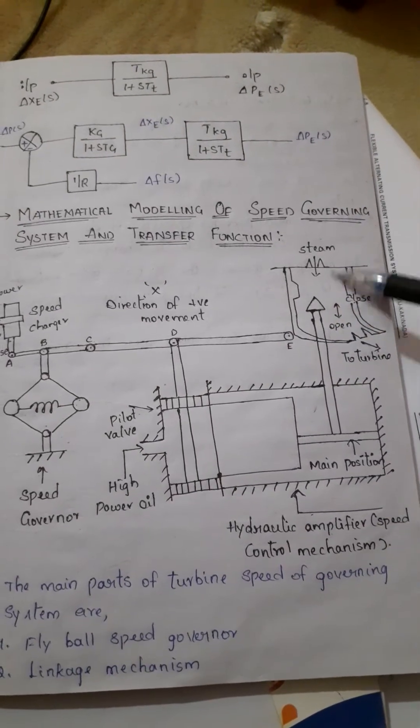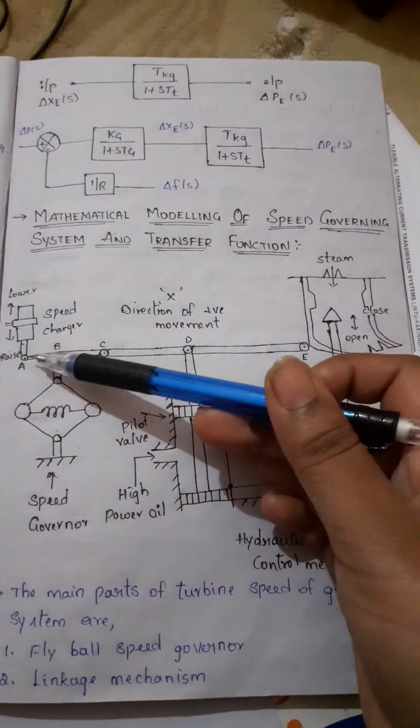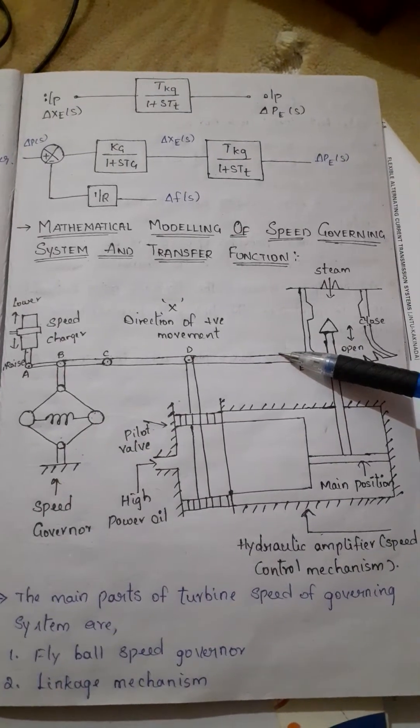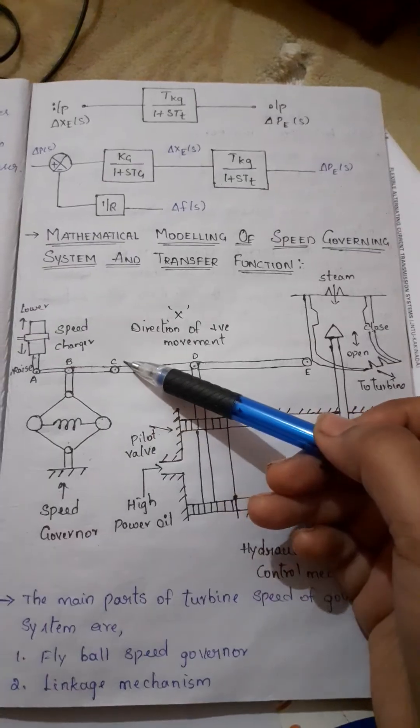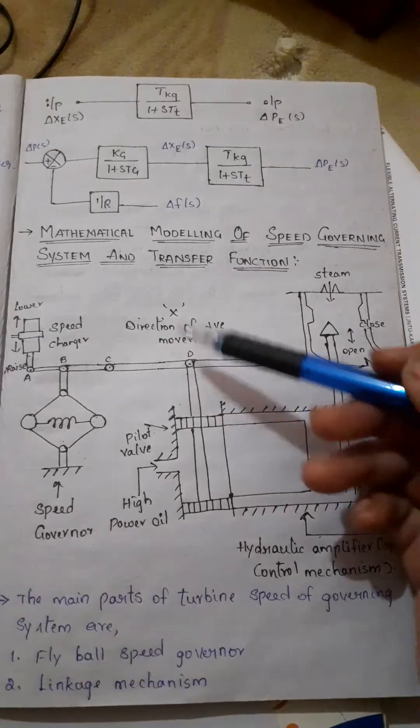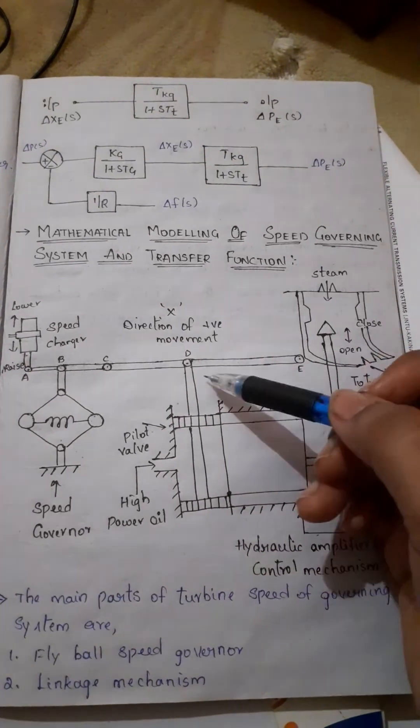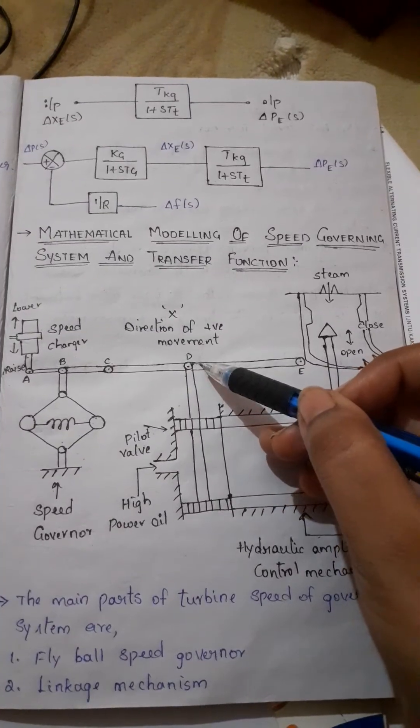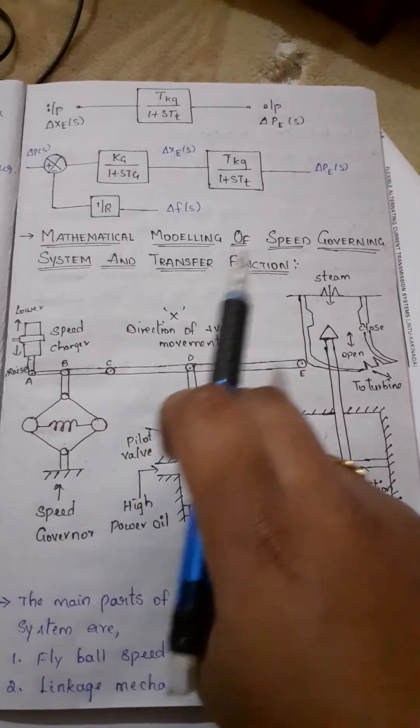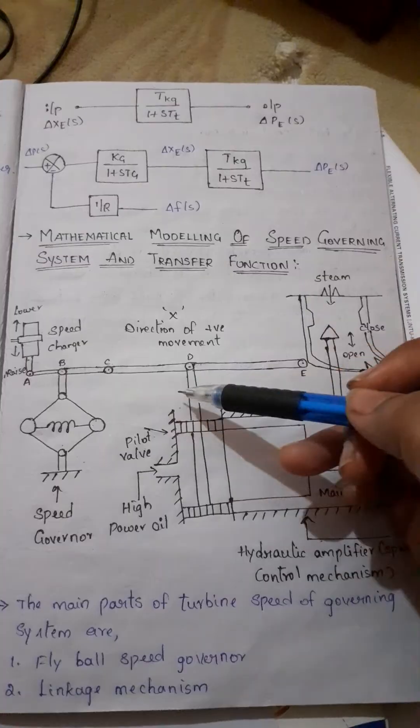The third one is the linkage mechanism. The linkage mechanism has two rigid links. One rigid link is ABC which is pivoted at point B, and another link is CDE which is pivoted at D. This linkage mechanism provides a movement to control the valve in proportion to change in speed. It also provides feedback from the steam valve movement.